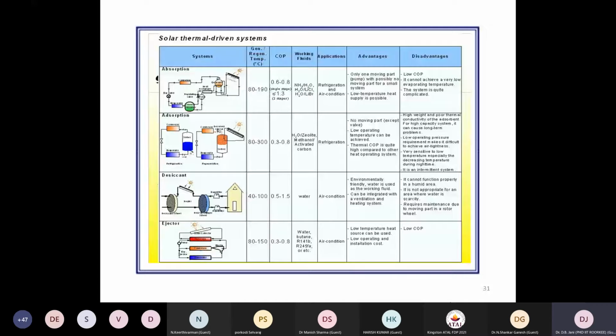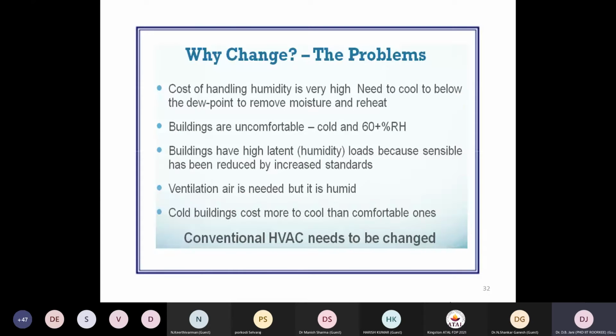From the comparison we see here, the regeneration temperature required for desiccant cooling is comparable, and its COP is intermediate as well as the highest among the different systems. So there may be great suitability for a desiccant cooling system to integrate with renewable solar energy. One question born in the mind of every HVAC user is whether there is any need to change the currently used HVAC system. Yes, definitely, because the conventionally used system may not be good wherever ambient humidity is high.